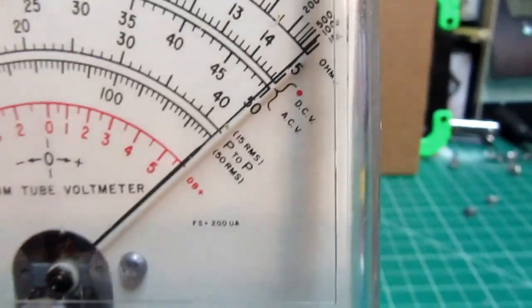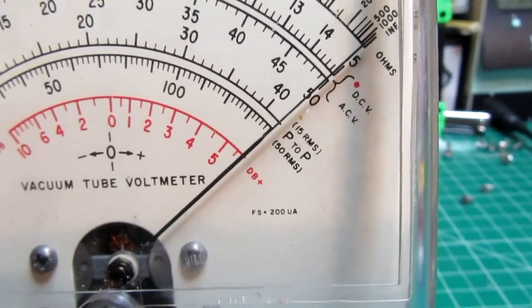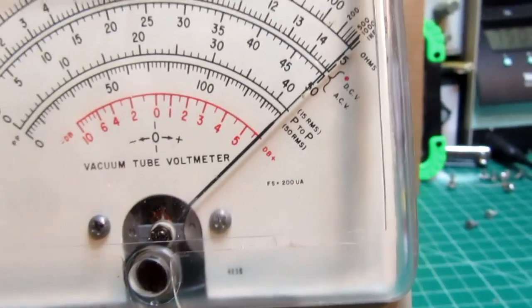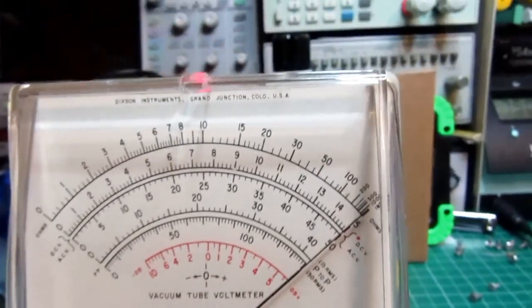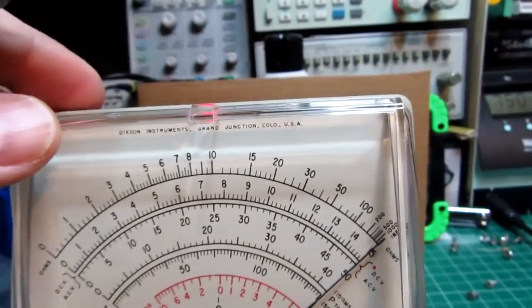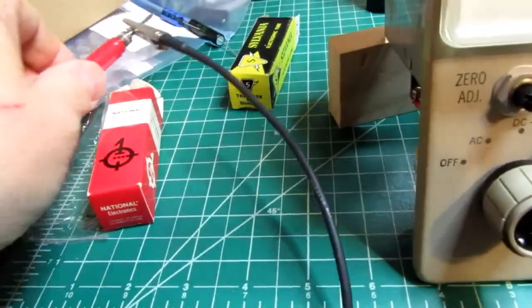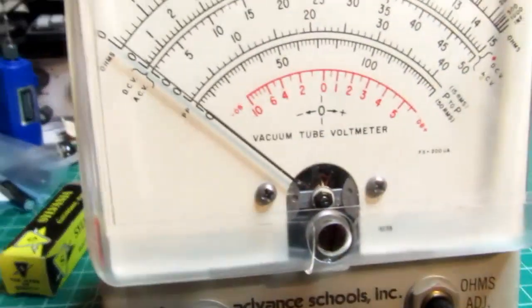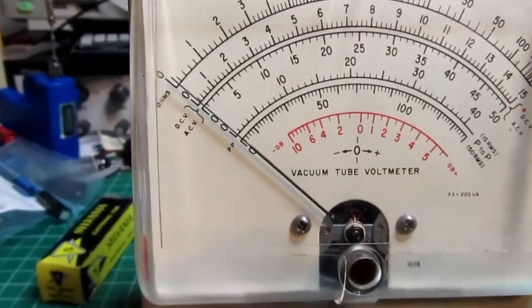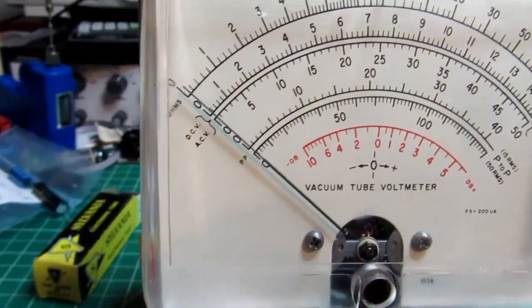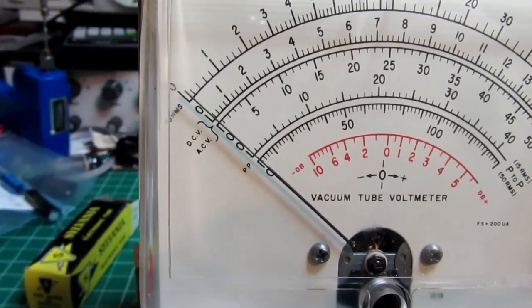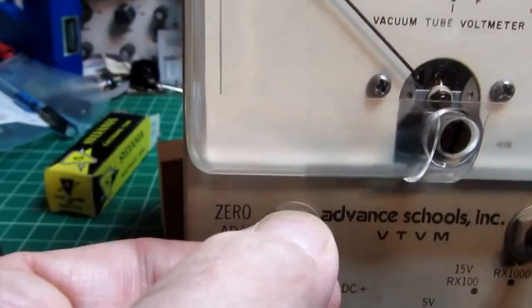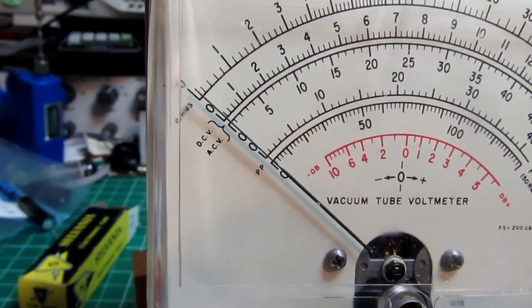So there's always this parallax I'm looking at here. Now it seems like it's reading a little low, but I'm kind of cheating here by trying to adjust this when the meter isn't completely warmed up. And so I have the test leads shorted out, and I'm verifying I'm getting a reading of 0, pretty much. These things are always a little drifty, so you have to adjust the 0 adjust with some frequency.